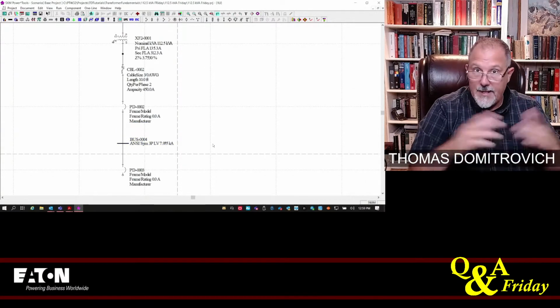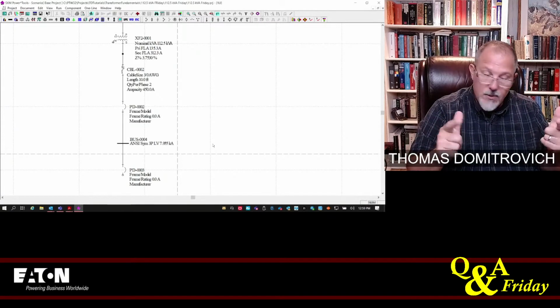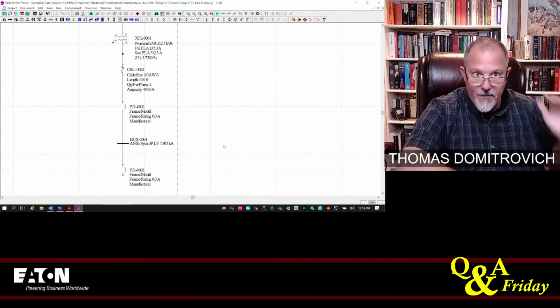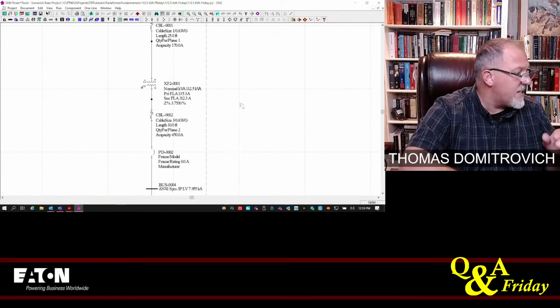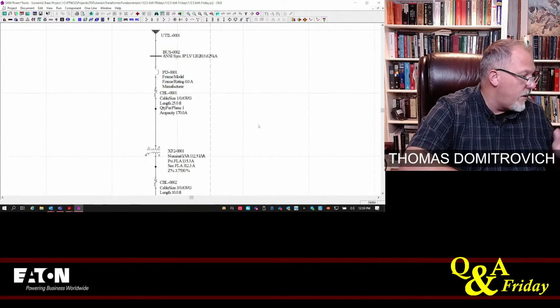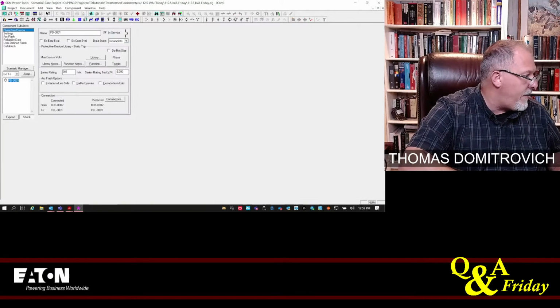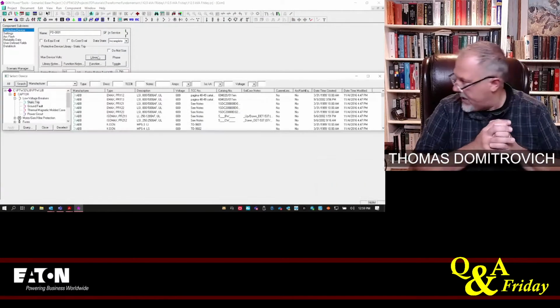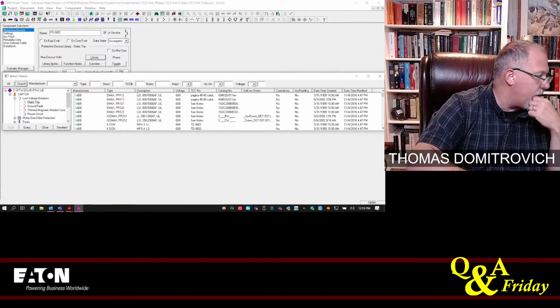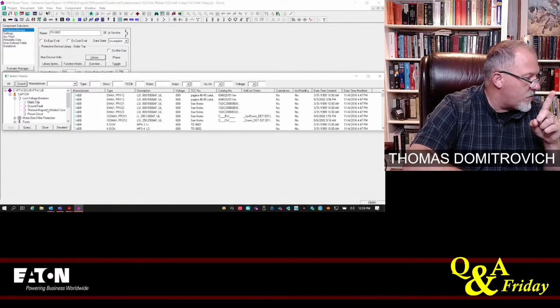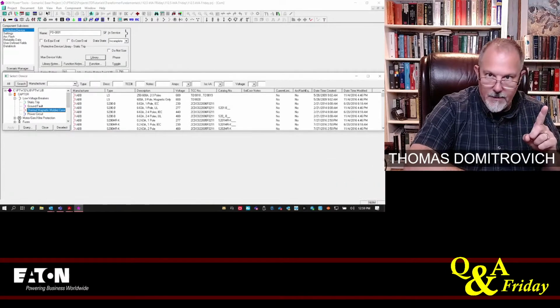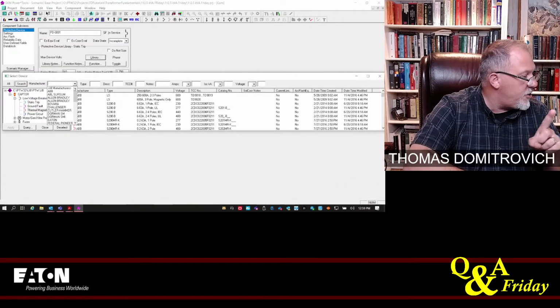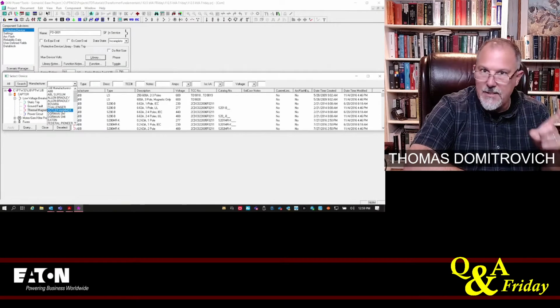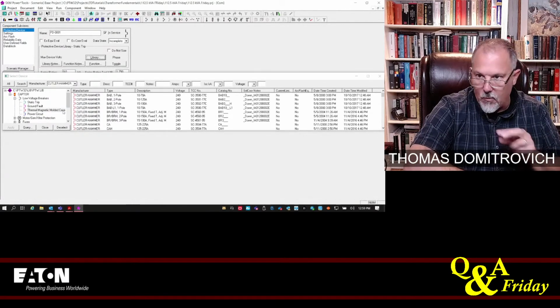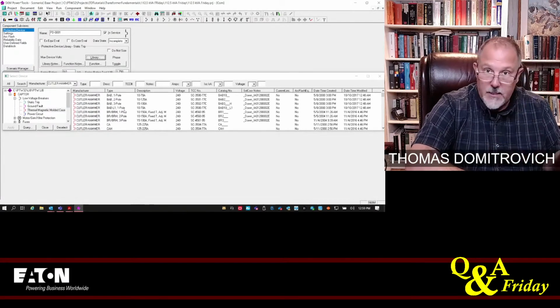7,955 amps. 10K breakers every day of the week, twice on Sunday. All right, so now I know my fault current. Let's plot my curves. Oh, I haven't picked the breaker. So we said on the primary, we were going to start with a 150 amp breaker. Remember, to work correctly, in any of these software applications, you have to filter everything to Eaton or Cutler Hammer or Westinghouse. Otherwise, it just doesn't work.